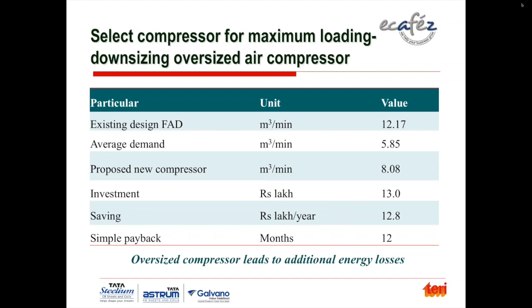Now, another measure, which is obviously an investment measure, not a free or best operating practice, is to downsize the compressor. One thing you need to remember is that any air compressor needs to be operated at maximum loading; usually it should be loaded 75-80% of the time. But usually we find in the audits that people purchase a larger size of air compressor, so the loading is only 50%, 60%, 70%. It is never loaded to 80% loading, which the compressor should be. So this typical example is replacing an oversized compressor with a smaller compressor.